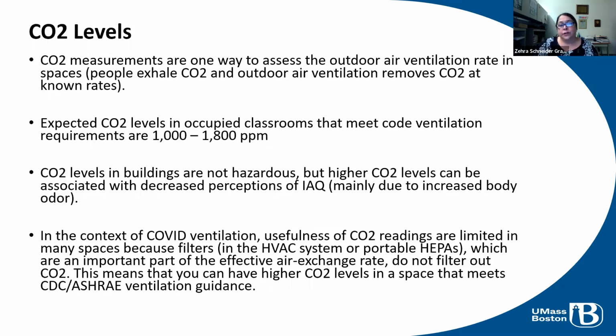Finally, just wanted to say a little bit about CO2 levels because there's been some discussion about that on campus. CO2 measurements are one way to assess the outdoor air ventilation rate in spaces. And we know that people exhale CO2 and that outdoor air ventilation removes CO2 at known rates. Expected CO2 levels in occupied classrooms that meet code ventilation requirements are 1,000 to 1,800 ppm. CO2 levels in buildings are not hazardous, but higher CO2 levels can be associated with decreased perceptions of IAQ. So think about stale air. If the air is not moving and it's just sitting, then you can get a perception that the air quality is bad, but it's not. It's not a sign of a hazardous condition.